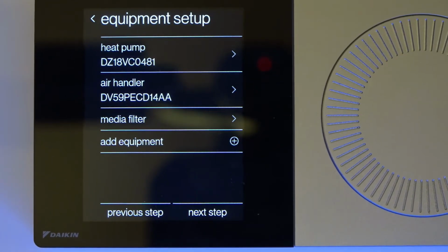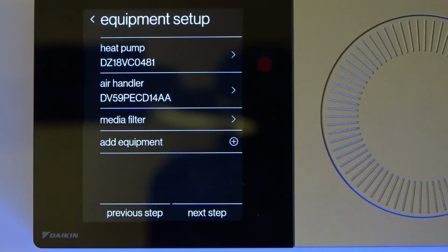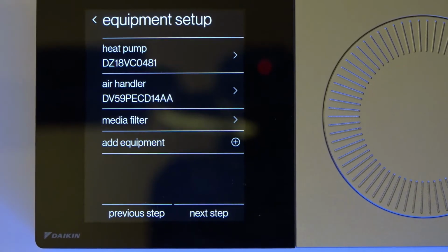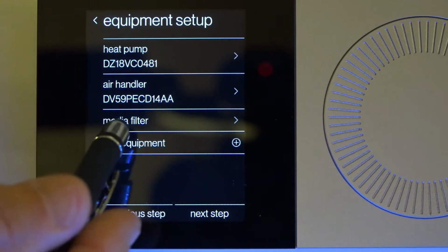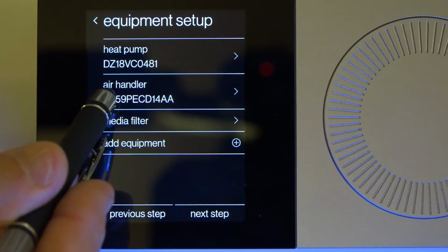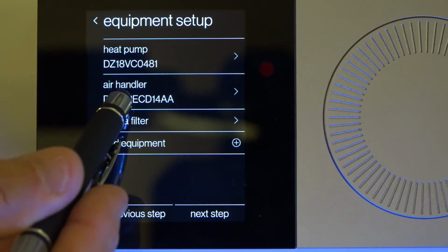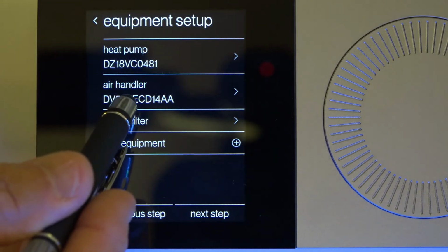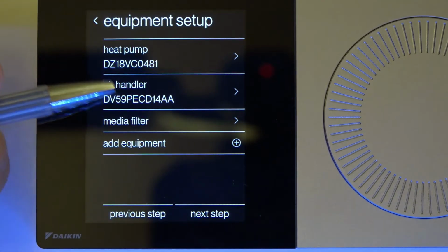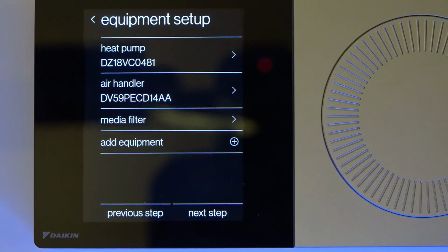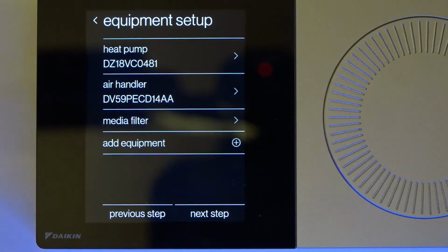It's an 18 SEER. The V stands for variable speed. C stands for communicating, and this particular board is for a 48,000 BTU unit, so a 4-ton. Now the DV is our Daikin variable speed air handler. It's a 59 PEC. The P stands for painted cabinet. The E is for electronic expansion valve, and there again, C stands for communications.